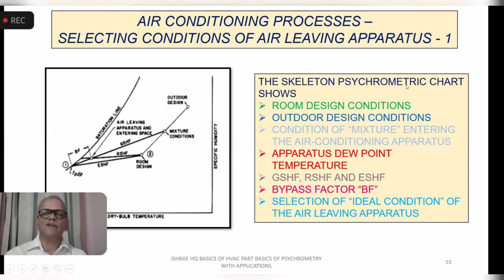So the skeleton is showing room design condition, which is here, outdoor design, which is here. The condition of the mixture entering, depending on the proportion of this, here it is 50-50. So it is halfway there. Apparatus dew point temperature, which is selected from the ADP chart, and the sensible heat factor. And then you get this bypass factor for the coil, and you get the ideal condition, which is here.